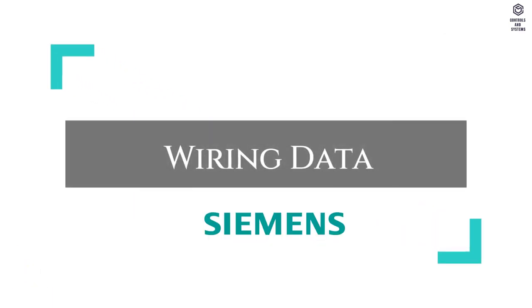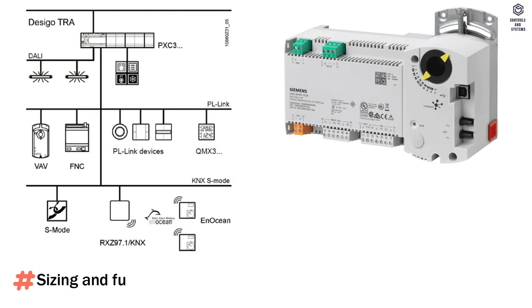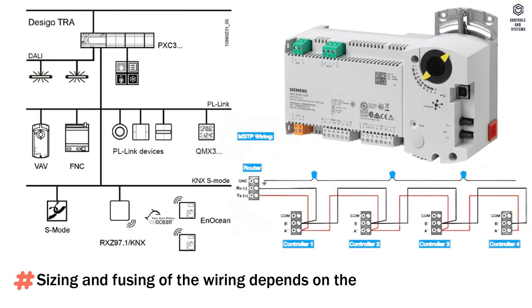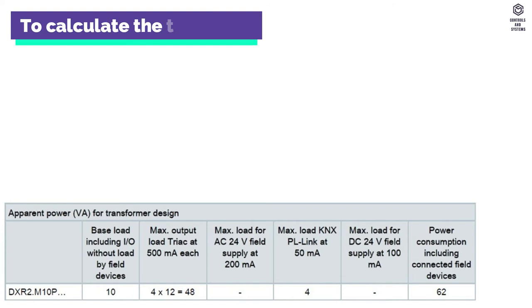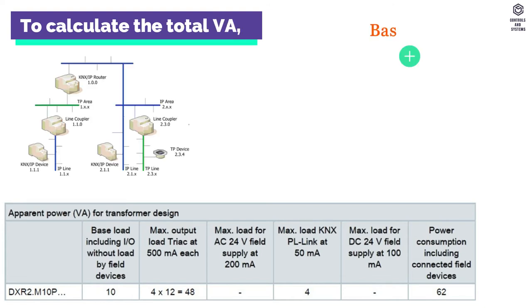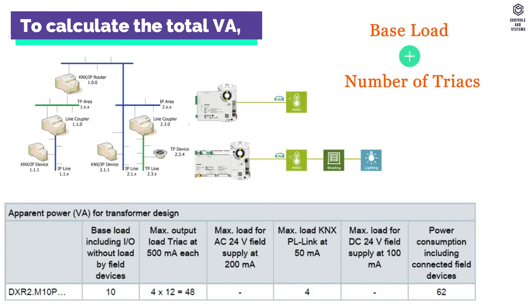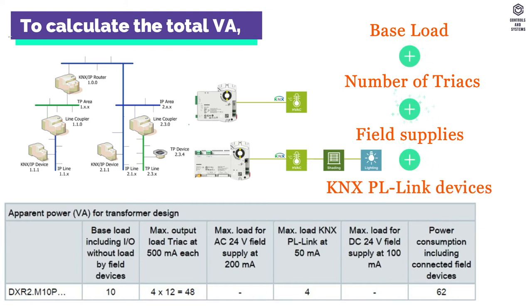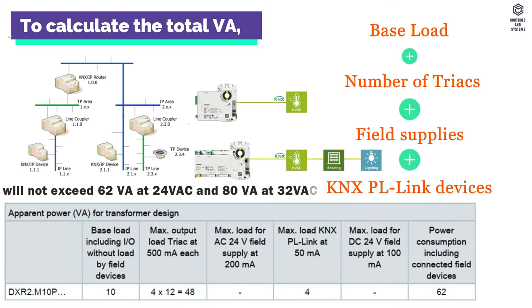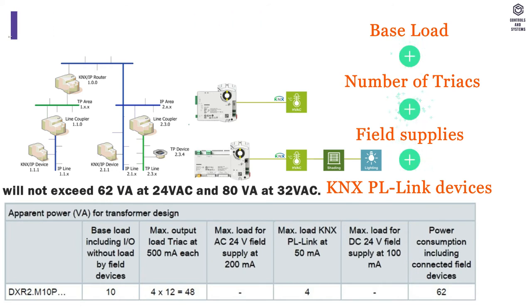Wiring data: sizing and fusing of the wiring depends on the connected load. To calculate the total VA, add the base load plus the number of TRIACs plus field supplies plus KNX PL link devices — will not exceed 62 VA at 24V AC and 80 VA at 32V AC.